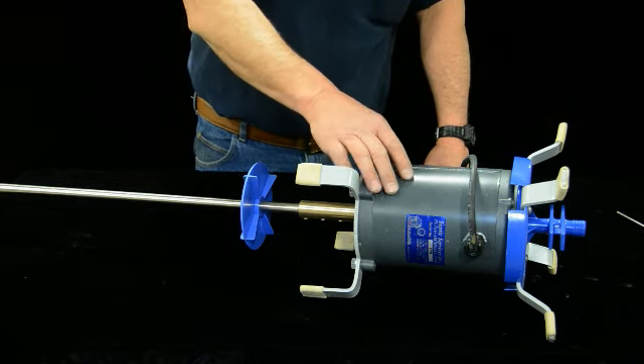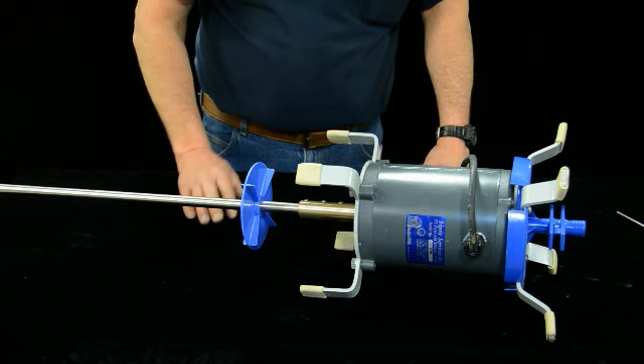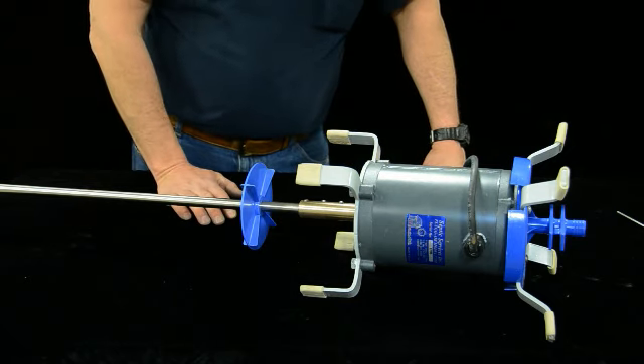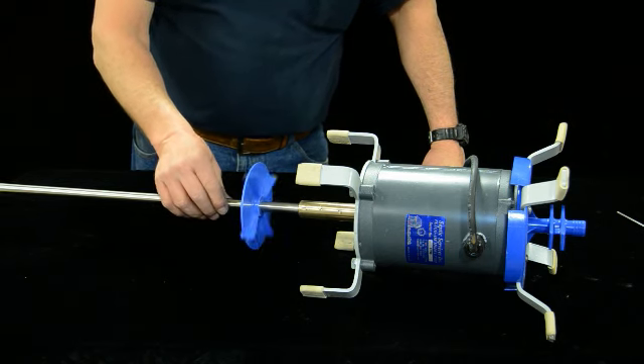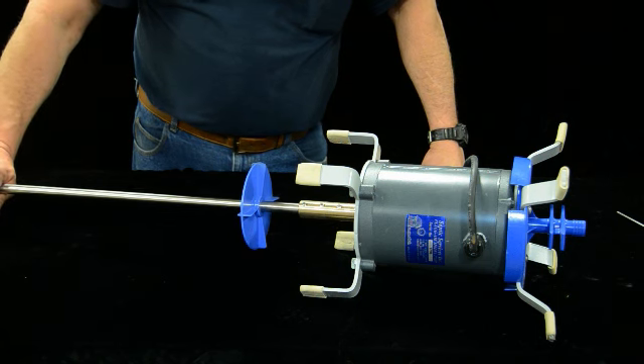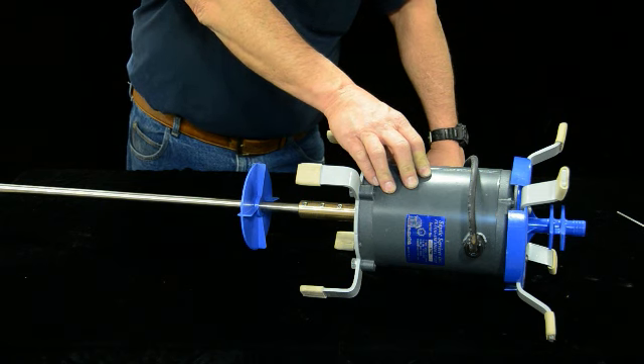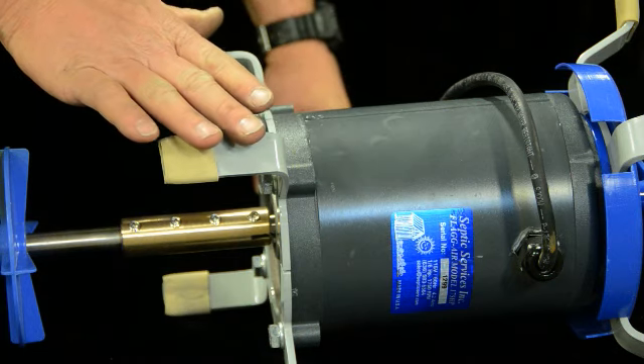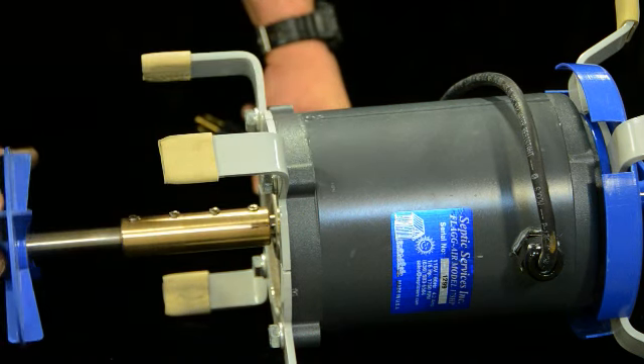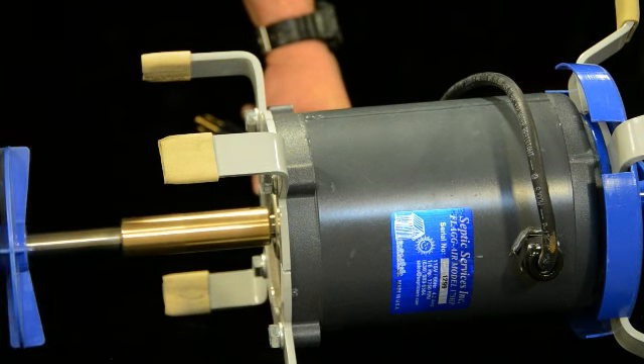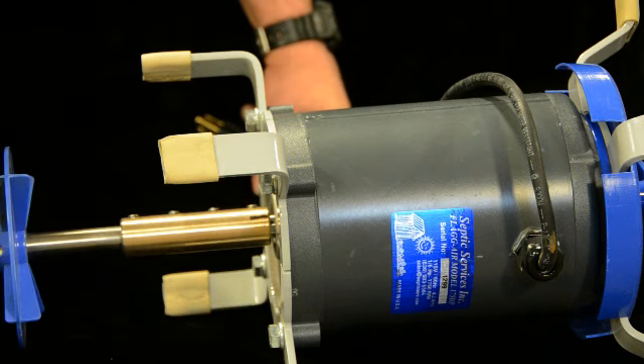And the other thing that's really important with these is the proper size breaker for the motor. If you hook this up without a control panel directly to a 15 or 20 amp breaker in the house panel, you will burn this motor up and you'll ruin it. Because as it builds up some hair on here or debris, it pulls more amps than the motor's manufactured to withstand and it'll burn it up. So because you're putting in a replacement unit or replacing one that's there, you need to figure out what caused it to go bad and be certain that you have the proper size mini breaker in that control panel for the unit that you're replacing.